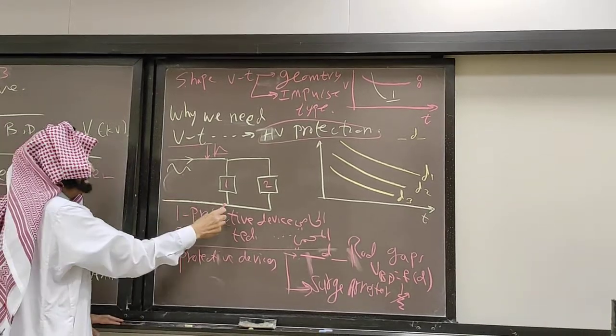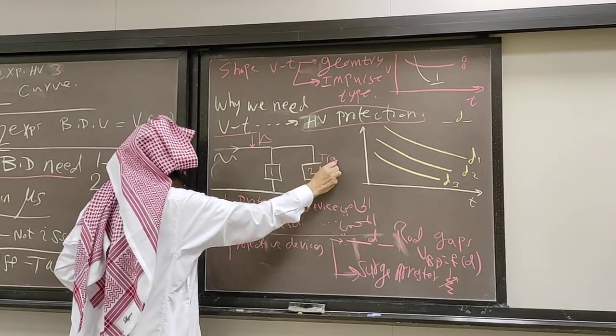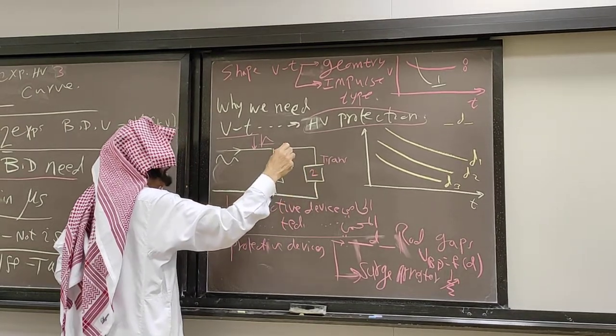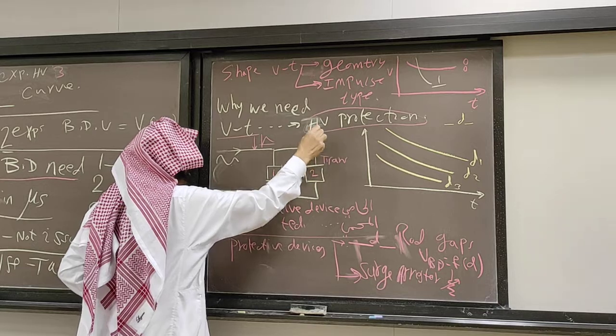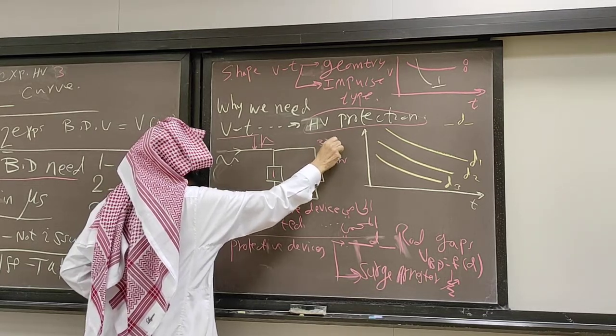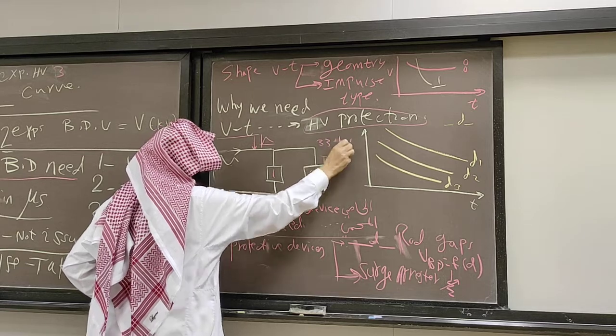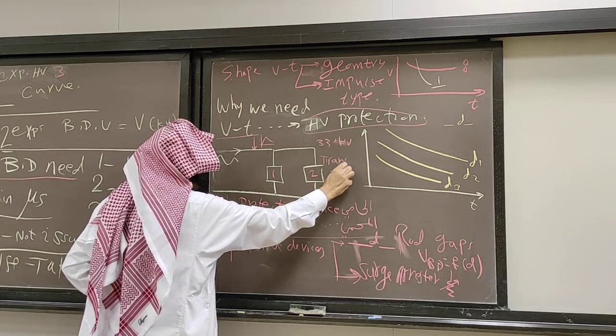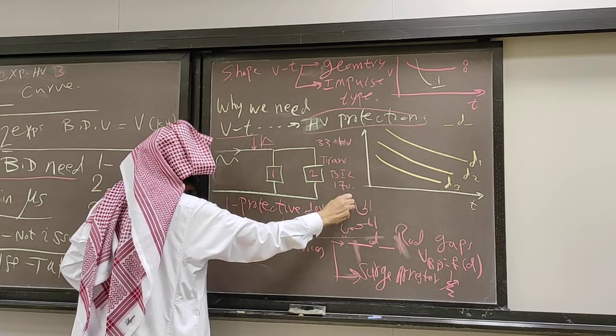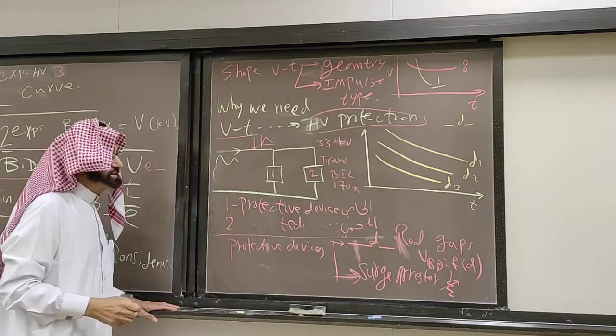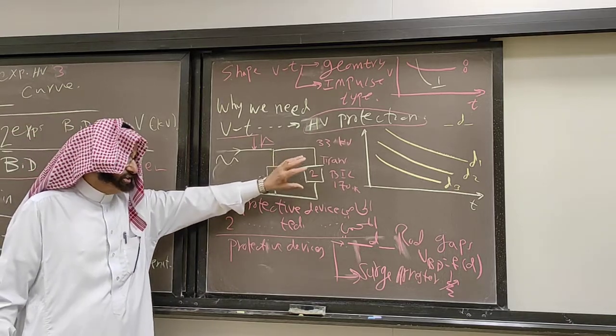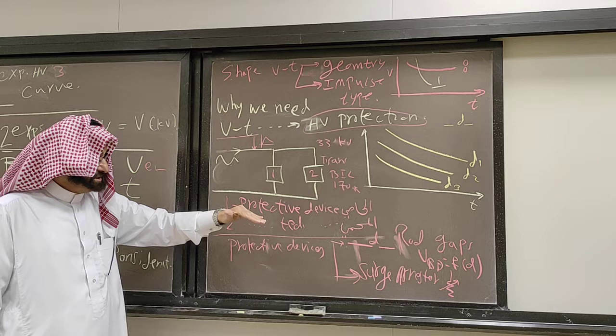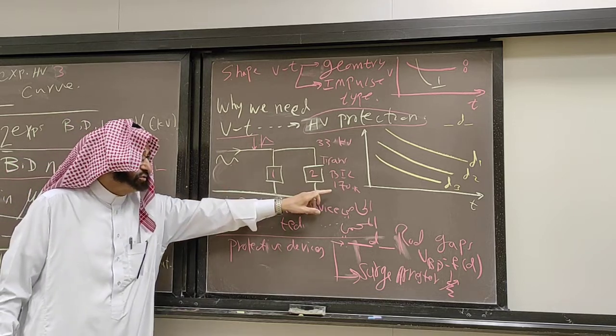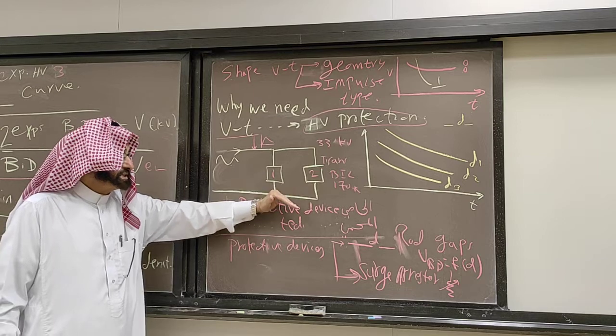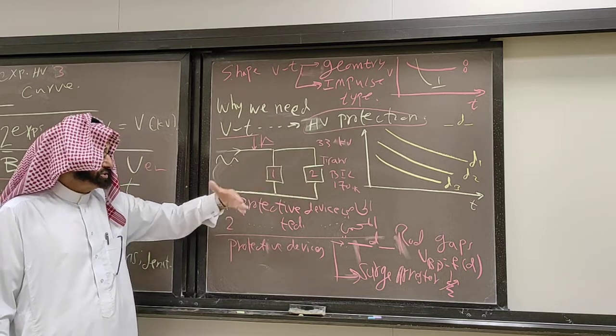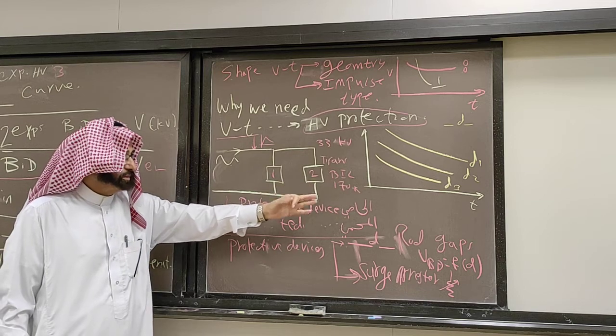So assume we have this system. This is a transformer, for example. The transformer can take, let's say, AC 33 kV. According to the standard, it has to take a BIL of 170 kV. So in the standard, they say when you have a 33 kV distribution transformer, it can take up to a 170 kilovolt impulse. If it is less, you have to test it before you use it in the system, at a 170 kilovolt impulse and 33 kV.